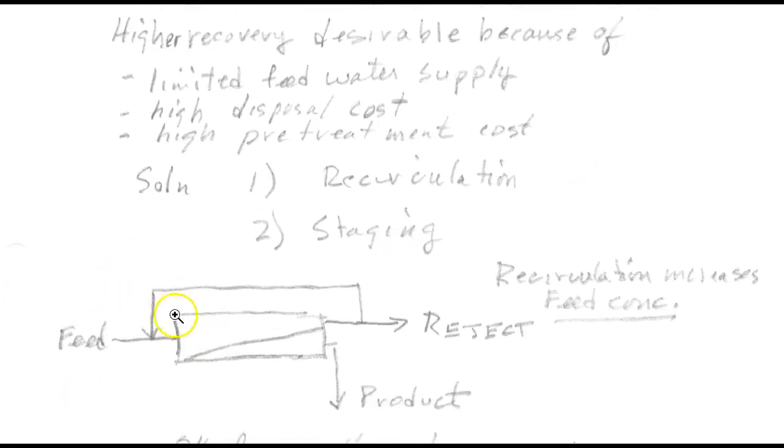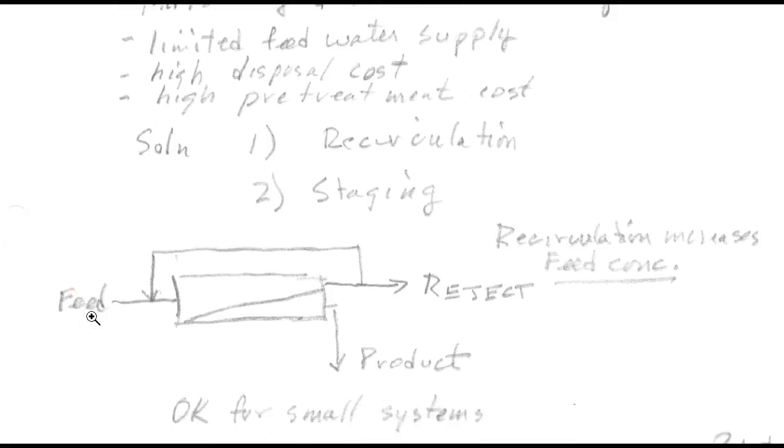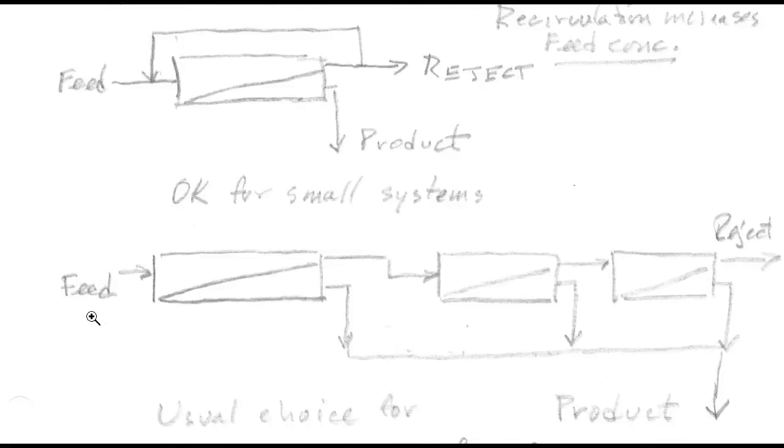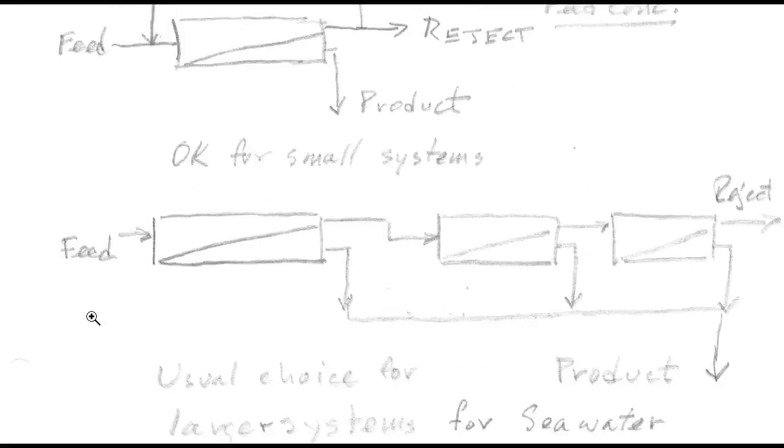Recirculation would look like this, where you're going around and around, and that would be a common practice for a smaller facility. The staging option is like this, where you would have several modules in series collecting the product off each one, and the reject stream from the first would go to the second and from the second to the third. This is the usual choice for larger systems for seawater.